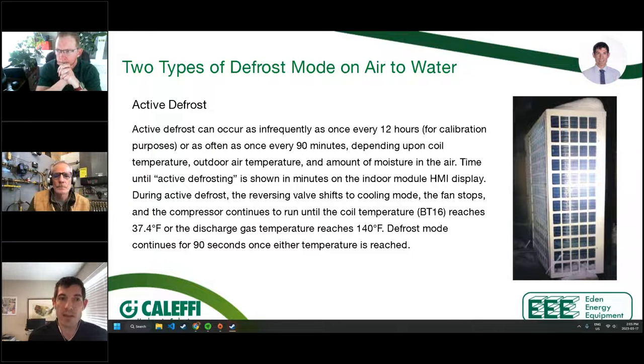So that's getting better. I think that's one of the critiques of air to water heat pumps in general: why would you put the machinery outside that you have to keep from frosting over, where it might be cold and you're making it colder? That seems like a bad idea. But this defrost has gotten so much better, and you're not just throwing it all out the window and running electric resistance to keep it from freezing all winter, like you may have been doing even just a decade or so ago with air to water heat pumps outside with a monoblock.